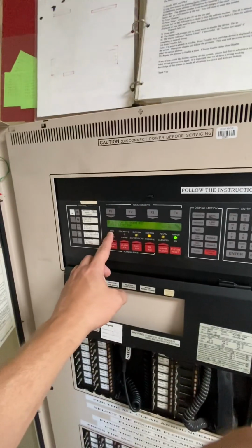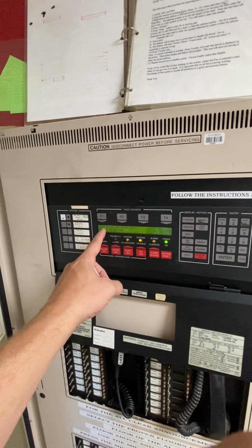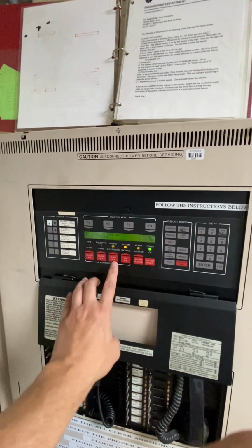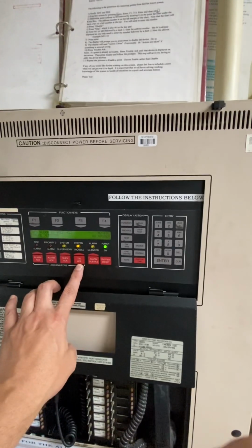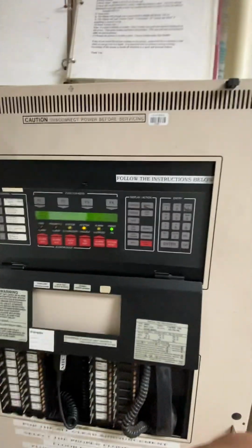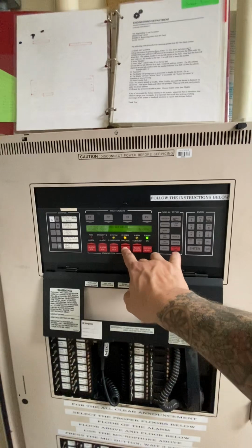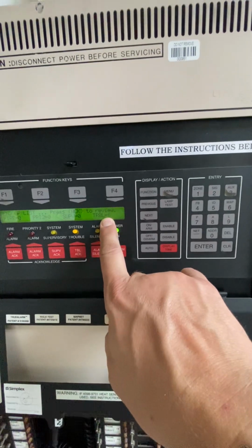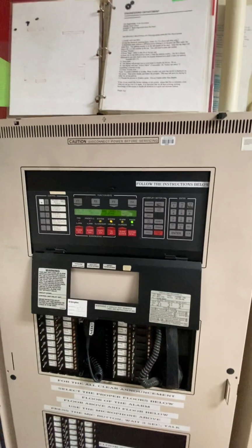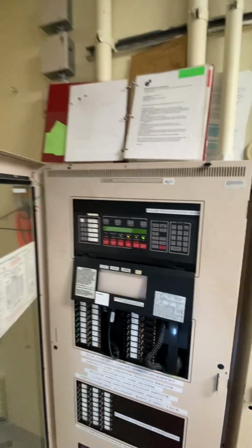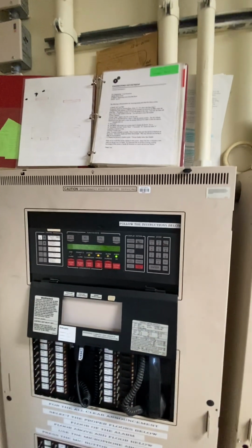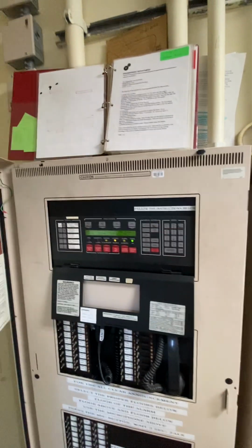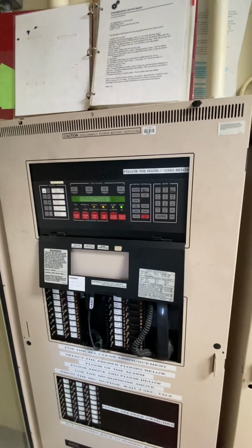So if it's one of these, alarm or supervisory, after you disable that point, we'll reset the system, and if it was in this column or this column, it will now appear in the trouble. So if it was a bad device and you have to disable it, it goes into the trouble bucket. So these numbers will go back to 0, and this number will go up 1 from where it was before. So that is in the situation where it's a pull station or a heat sensor or a smoke detector that is broken or having problems. We just want to disable it from the system so that it doesn't continue to create alarm events and call the fire department out.